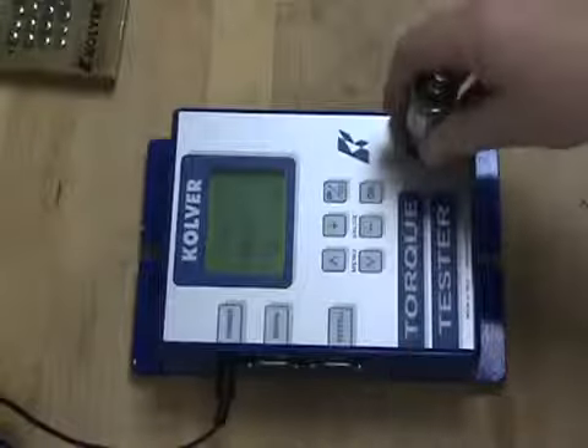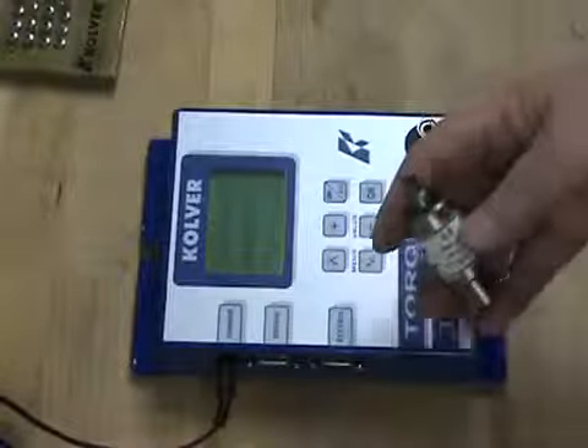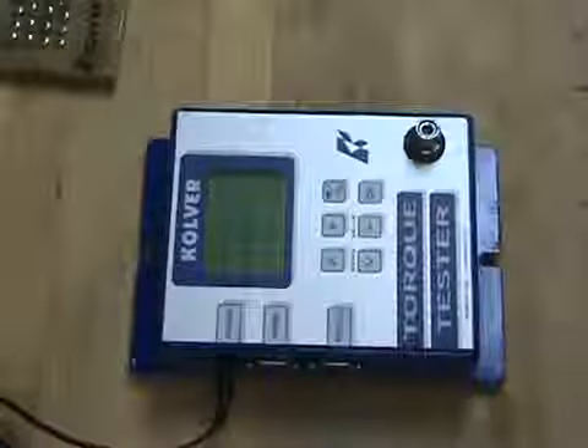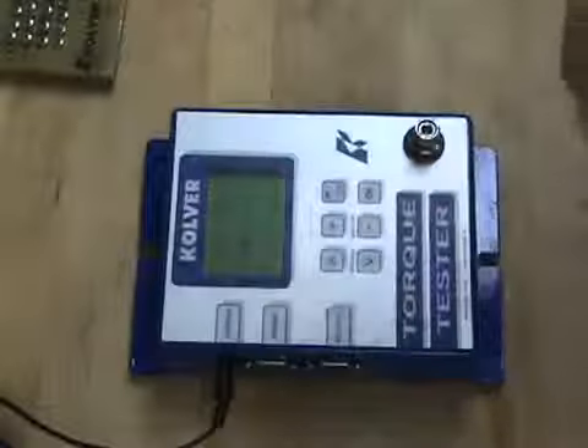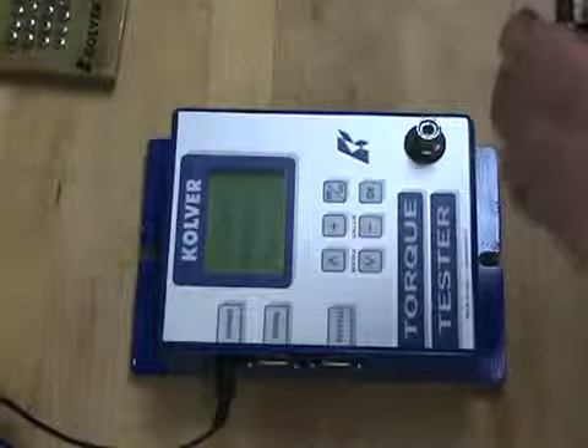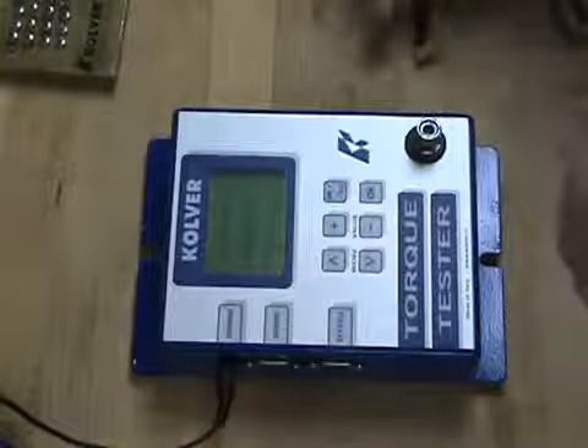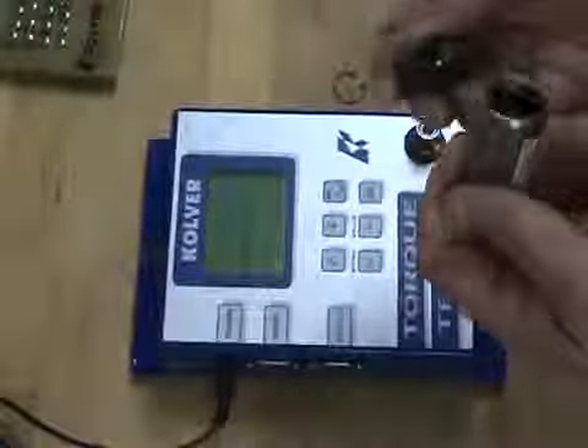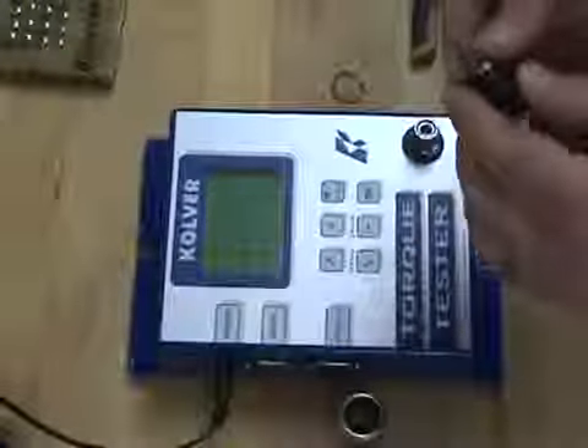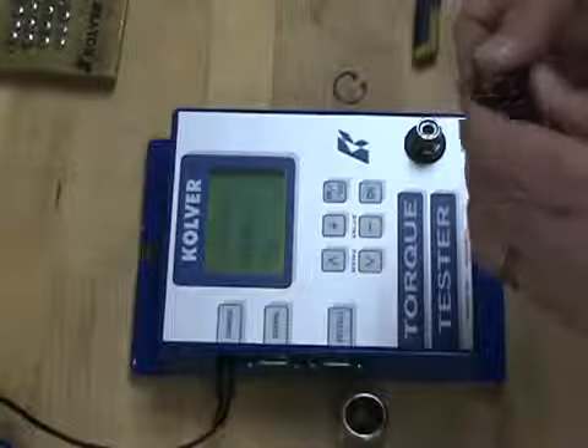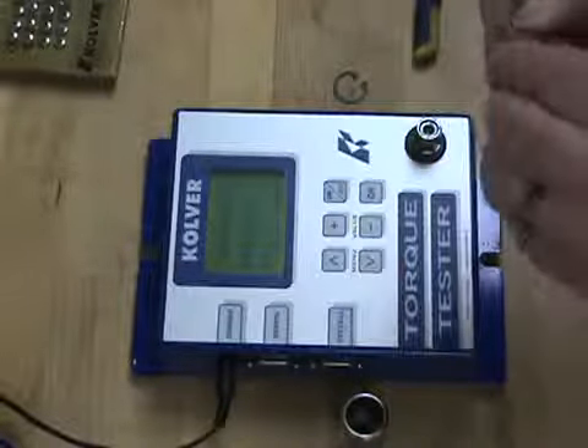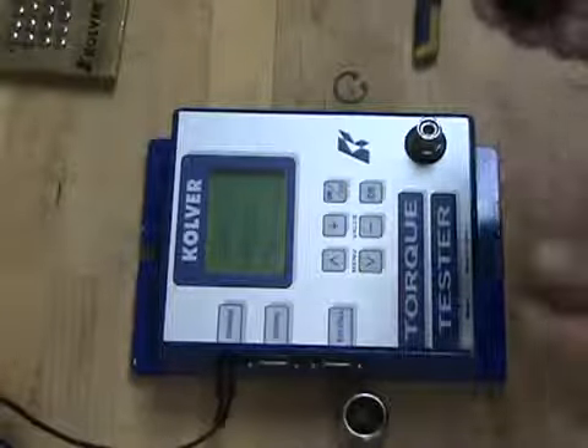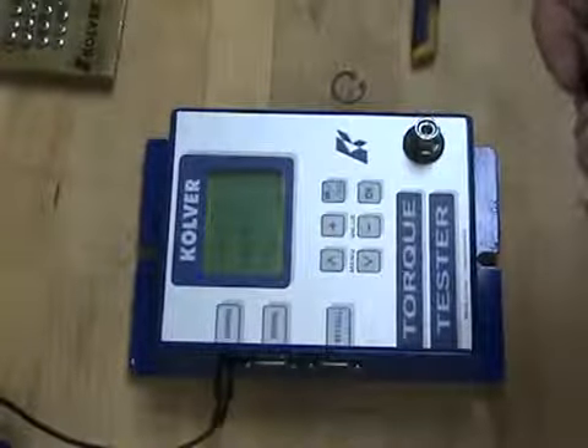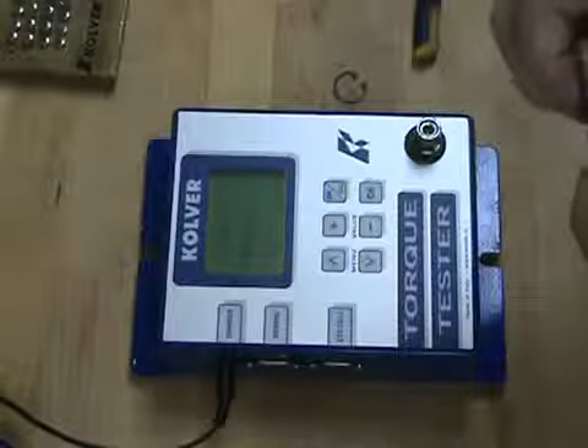All right, most importantly, to have set up and ready for your application is the joint simulator. This simulator comes as a medium joint from the factory, but you really want to remove the retaining ring and all the Belleville washers that are in here. These Belleville washers make up a spring, and like I said, from the factory, they come set as a medium joint. Your specific application may require you to set those more to a hard joint or a much softer joint.